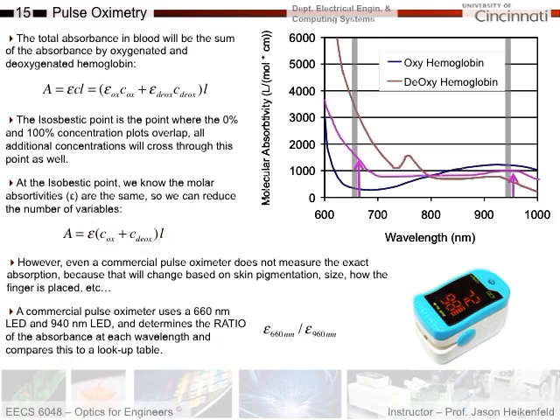We're still left with path length, and we need to deal with skin pigmentation, size, path length, and placement. A commercial pulse oximeter uses two wavelengths — typically 660 nanometers and 940 nanometers. They look at the ratio between the measurements at those two wavelengths, compare it to a lookup table knowing where the spread should be, and from that they can predict the concentration of oxygenated versus deoxygenated blood. That's why two wavelengths are used — it's essentially an exercise in reducing as many variables as possible through multiple wavelength measurements at the right wavelengths.